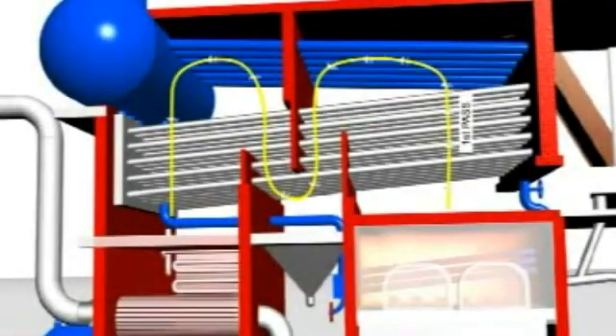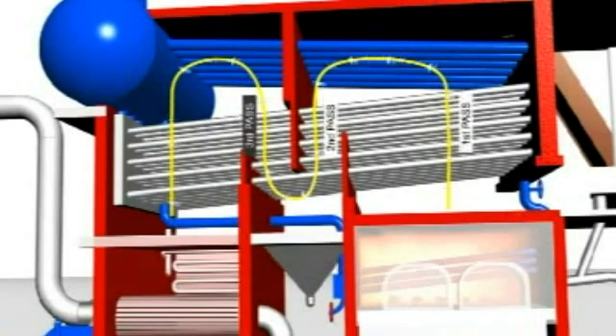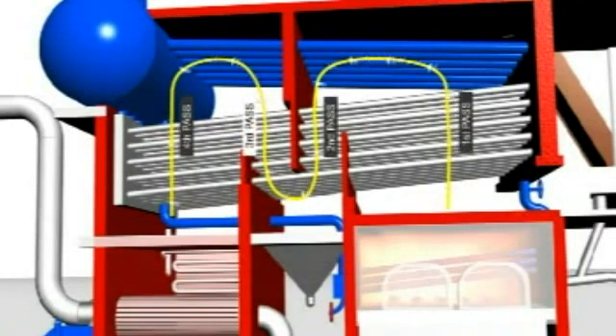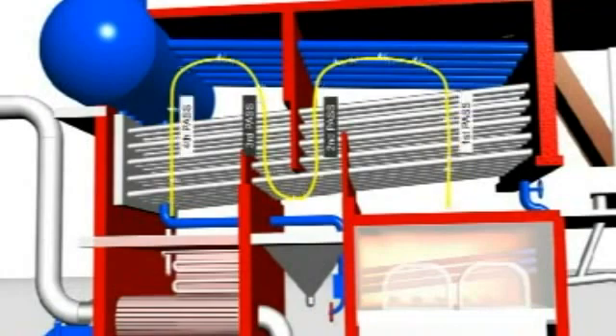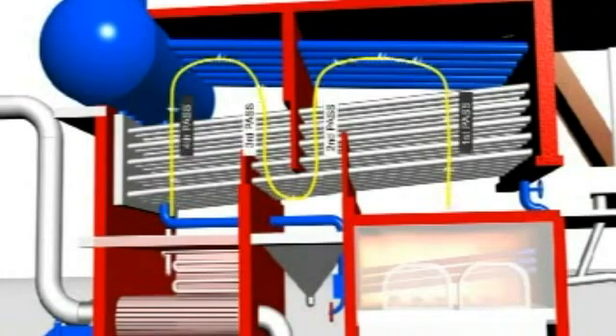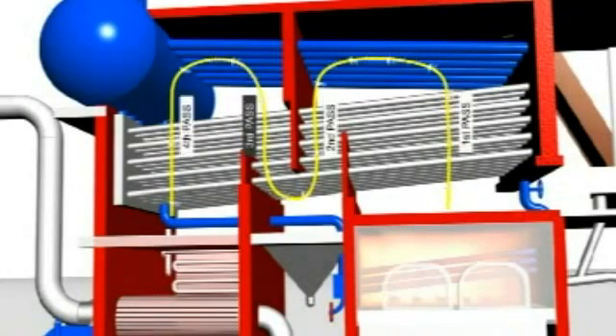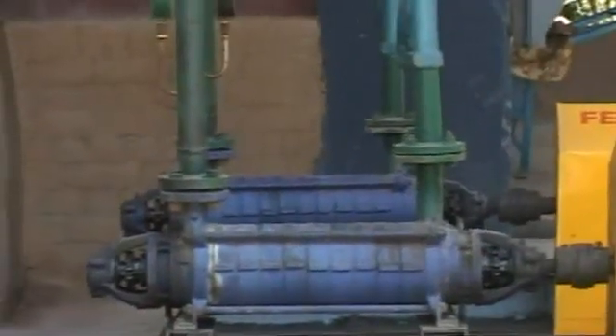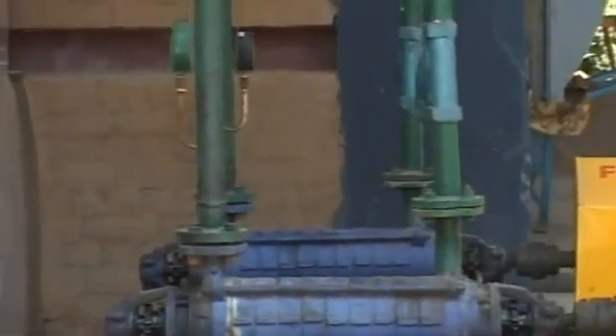The flue gas passes over the bank tubes for the first, second, third, and fourth passes, and is sent out to the waste heat recovery unit, which includes the air preheater and economizer. A feed water pump supplies water through the waste heat recovery economizer to the boiler drum.